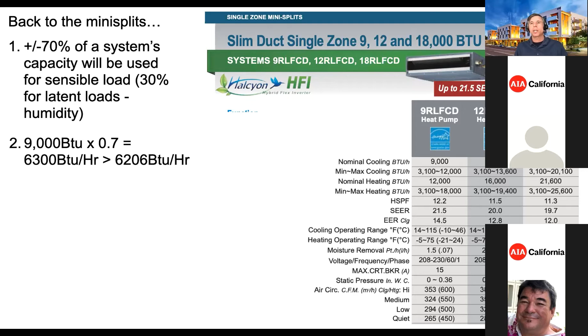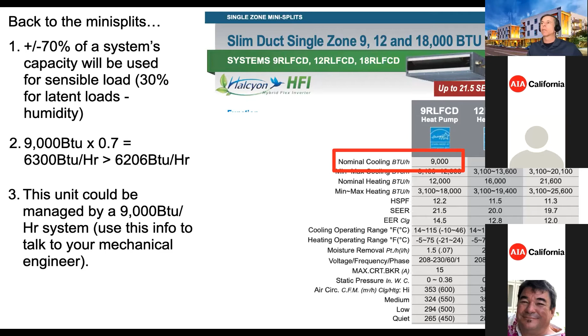So if I go with 70% as my sensible capacity of that system, and I look at the smallest system, 9,000 BTUs per hour is my maximum, times 0.7 equals 6,300, which is just bigger than that 6,200. So I like the 3/4 ton system here. I'm going to drive my mechanical engineer crazy because he wants to go with 1.5 tons. I'm going to show him my calculations, and we're going to haggle, and he's going to come around. I promise you. Okay, so the loads here could be managed by 9,000 BTU systems. So this is a great piece of information for your mechanical engineering discussions.